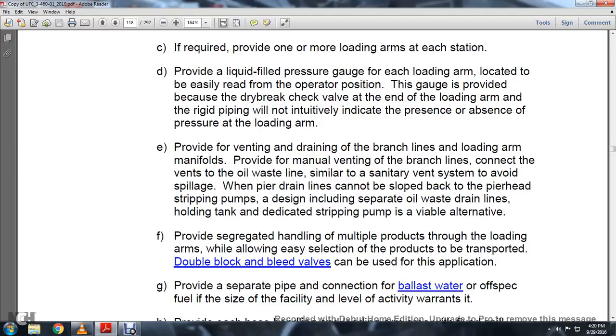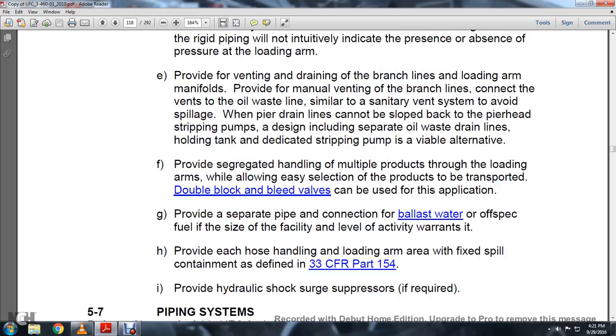Provide venting and draining of the branch lines and loading arm. At the manifolds, provide manual venting of the branch lines, connecting the vent to the oil waste line and similar to the sanitary vent system to avoid spillage. When the pier drain lines cannot be sloped back down to the pier head, a stripping pump design, including separate oil waste drain lines, a holding tank, and a dedicated strip pump, is a viable alternative.